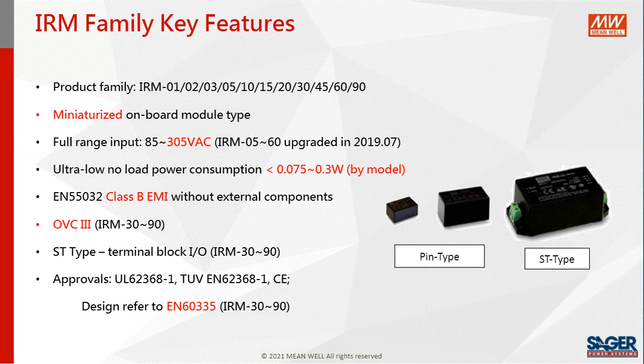Some models even draw less than 0.075 watts — very impressive. For higher wattage models, there's also over voltage category 3 certification. Over voltage category is more relevant in European applications, and it determines the different areas or locations where the power device can be installed. Over voltage category 3 is already sufficient for most of these power monitoring and power metering applications.